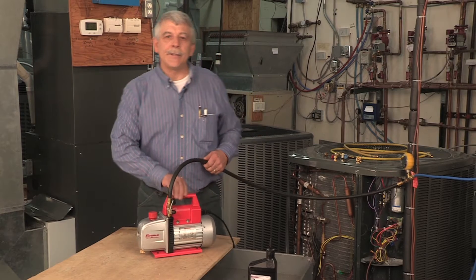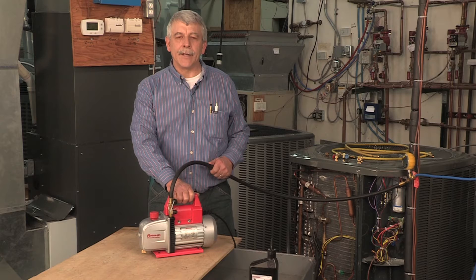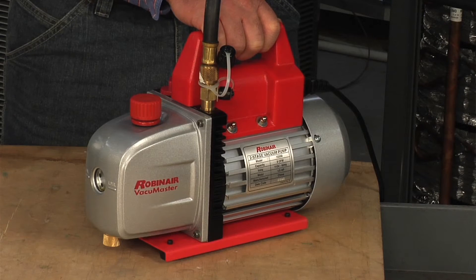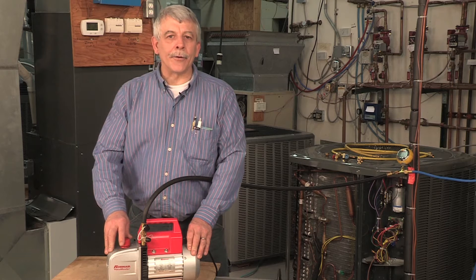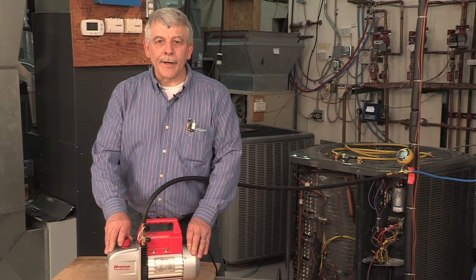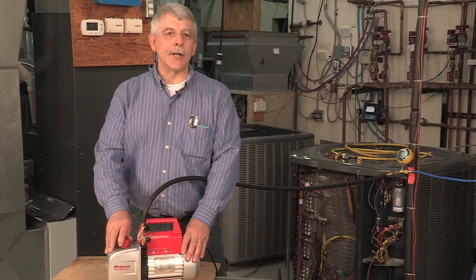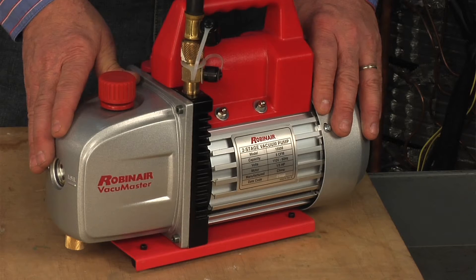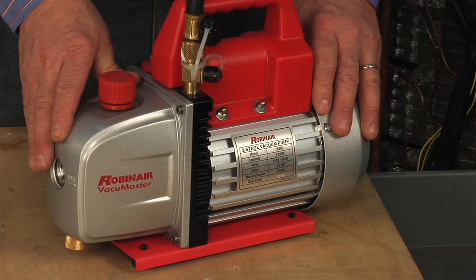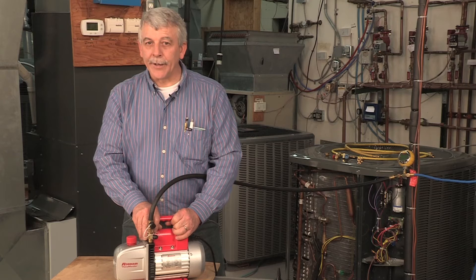A two-stage design removes air and moisture from the system quicker and more thoroughly, with the second stage vacuum leading to a deeper ultimate vacuum level. The heavy-duty one-third horsepower motor features a rotary vane, steel bearing, high-torque design for easy start-up and efficient operation. The new cast aluminum reservoir design reduces weight and creates a strong, durable pump — much lighter than the 28 to 30 pounds you'll find in the field.